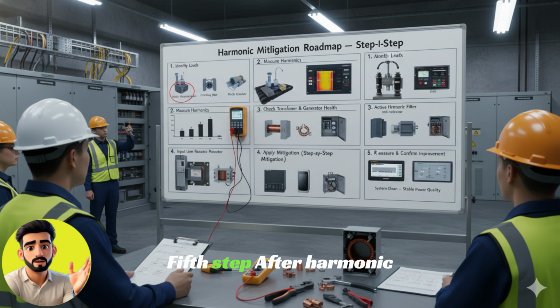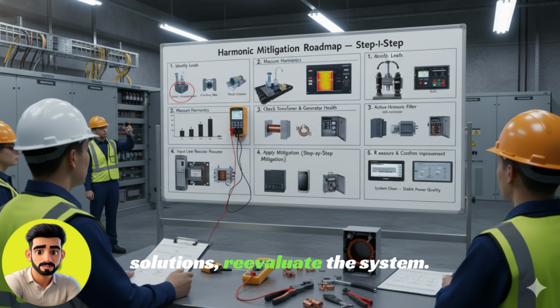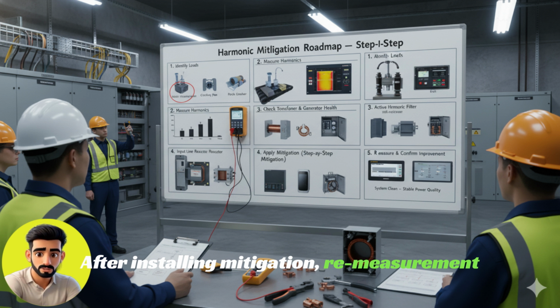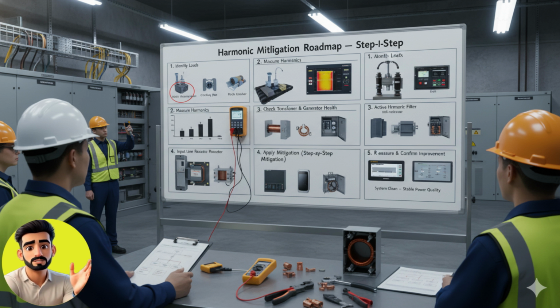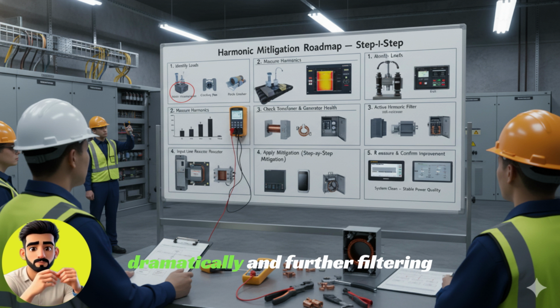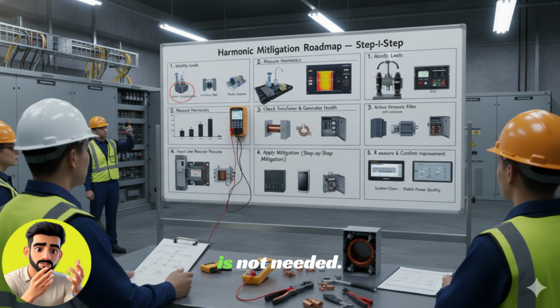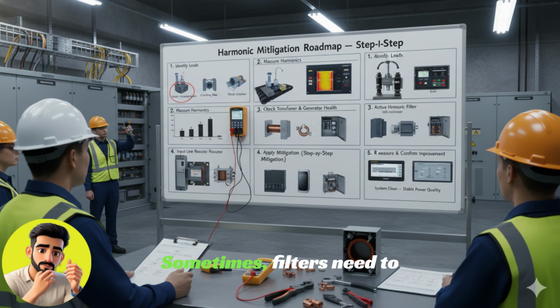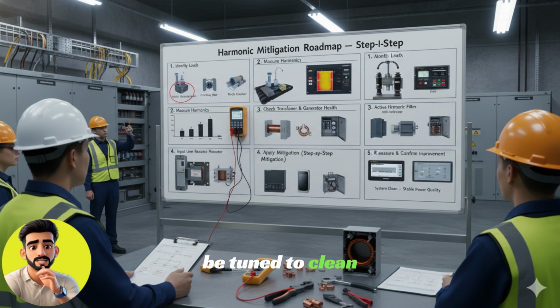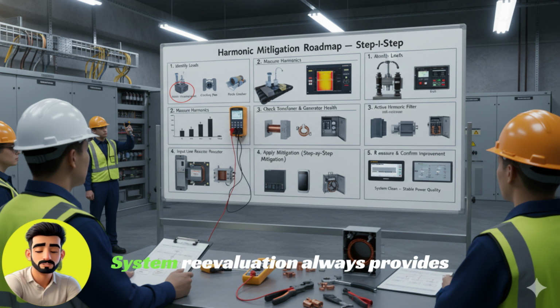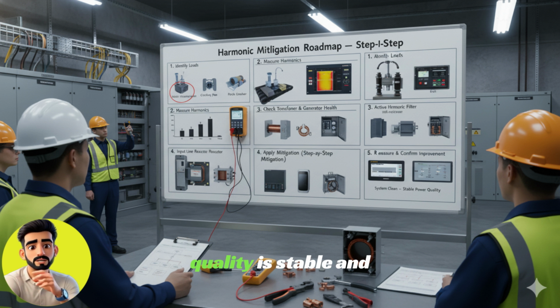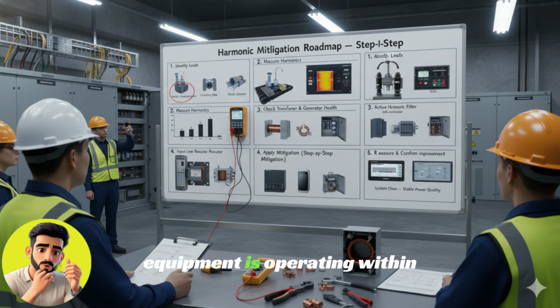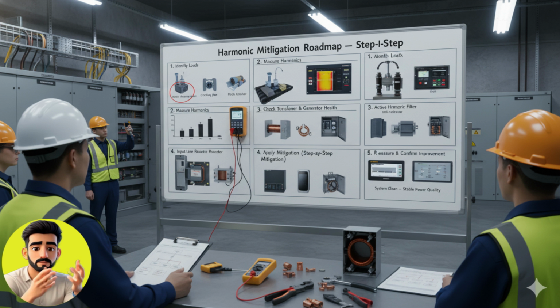Fifth step, after harmonic solutions, re-evaluate the system. After installing mitigation, remeasurement is important. Sometimes, immediately after installing line reactors, harmonics reduce dramatically and further filtering is not needed. Sometimes, filters need to be tuned to clean the harmonics. System re-evaluation always provides final confirmation that power quality is stable and equipment is operating within safe zones.